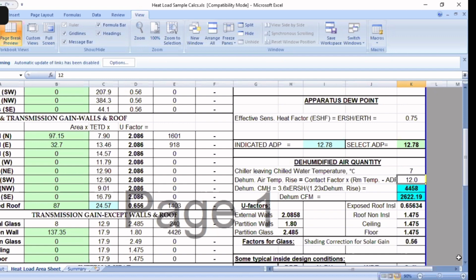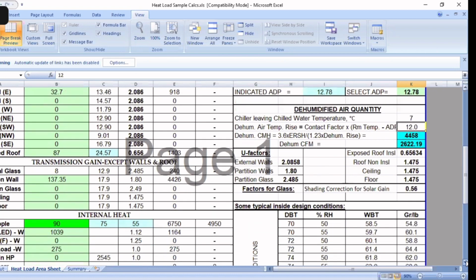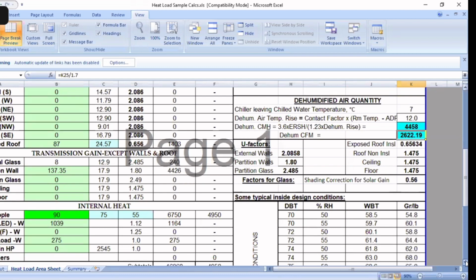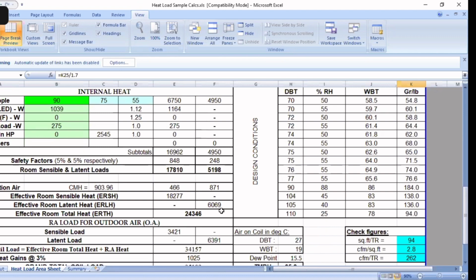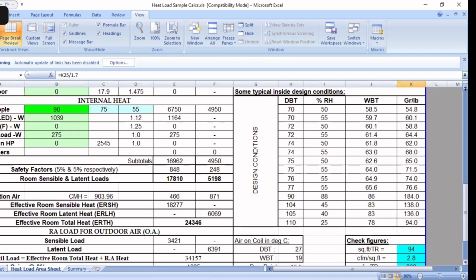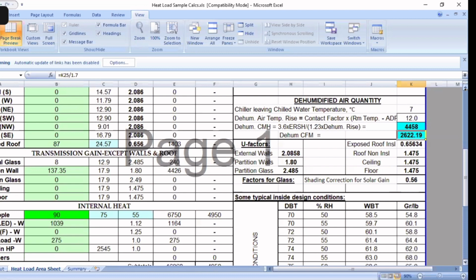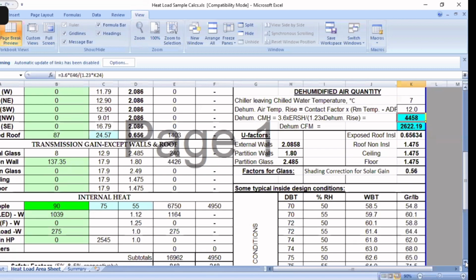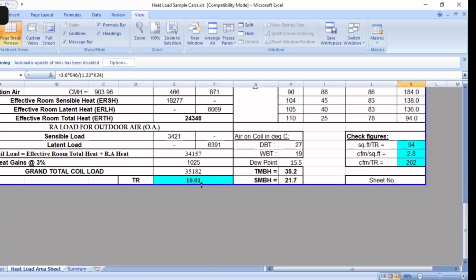So I have calculated the dehumidified air quantity from K25. It has come from here. Where is K25? Dehumidified air quantity. It has come from the essential, this is the ESH, equivalent room sensible heat, ERSH. So from ERSH I calculate the dehumidified air quantity here. So I get the dehumidified air quantity and my tonnage.